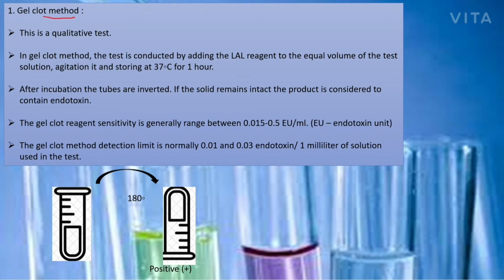So it is a qualitative test. What does qualitative test mean? It means that it only shows whether the endotoxin is present in the particular sample or not. It doesn't give us a range of how much endotoxin is present, but it only determines the presence of the endotoxin in the sample.